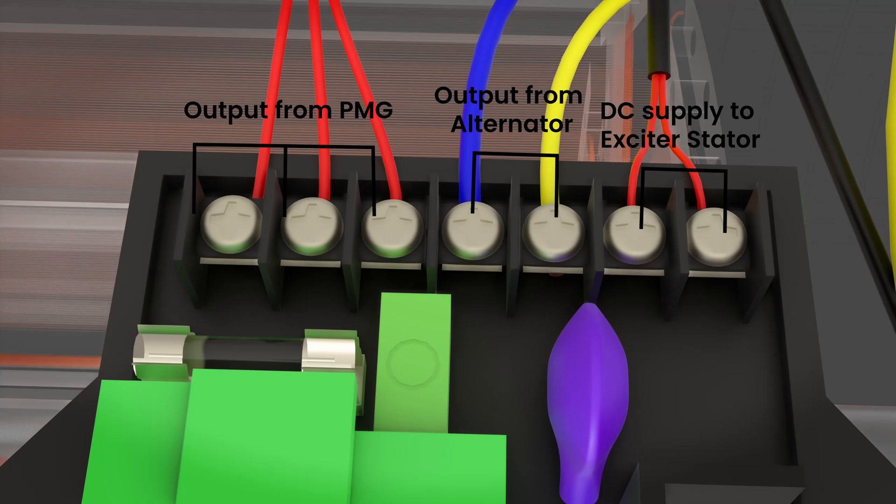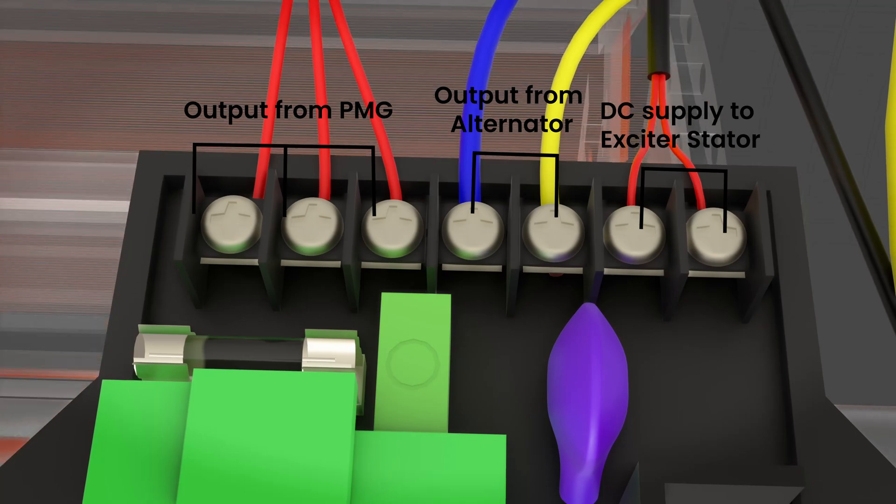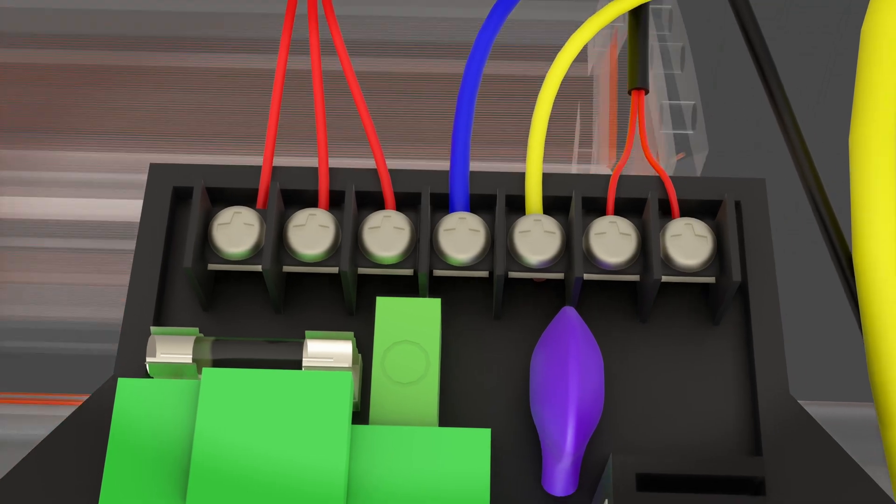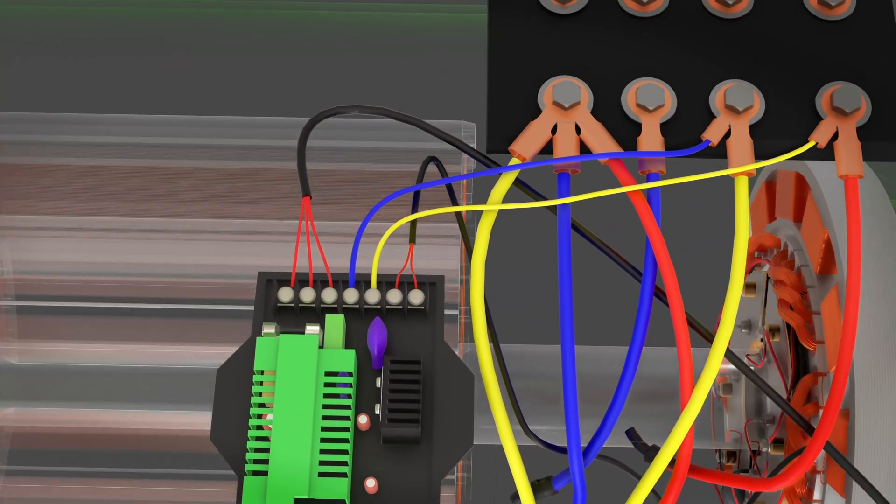Two terminals from the main alternator output are connected to the AVR for voltage sensing. The AVR continuously senses the voltage from the alternator terminals and compares it to a stable internal reference voltage.